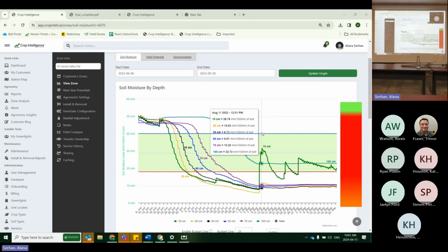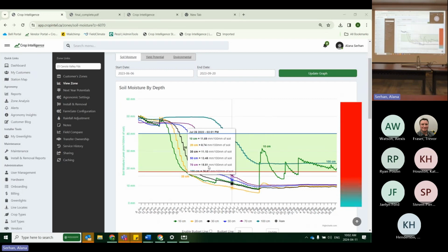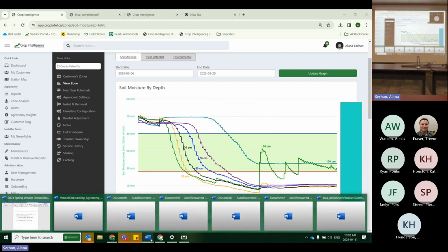Any other questions? How resistant are these probes when you're pushing them into the ground? Do they just fall in, or do you push them in after you drill a hole? There's going to be resistance because air pockets get trapped underneath the probe. We'll show you outside once we go through the whole process, and you can do it yourself by all means. So yes, there will be resistance. They don't just fall in and stay there. It's due to the consistency of the slurry that we mix. It has to be that consistency so that it makes proper contact with the probe.